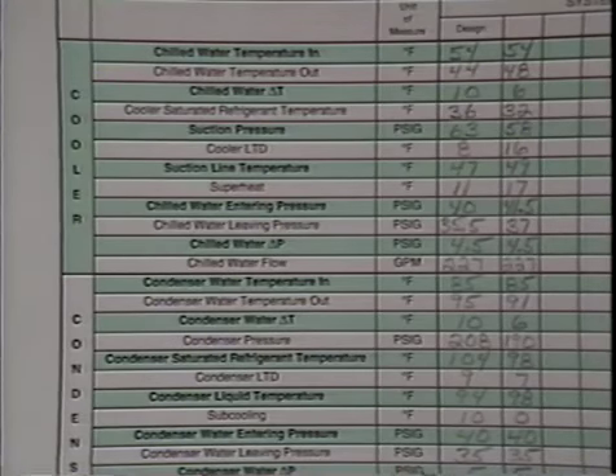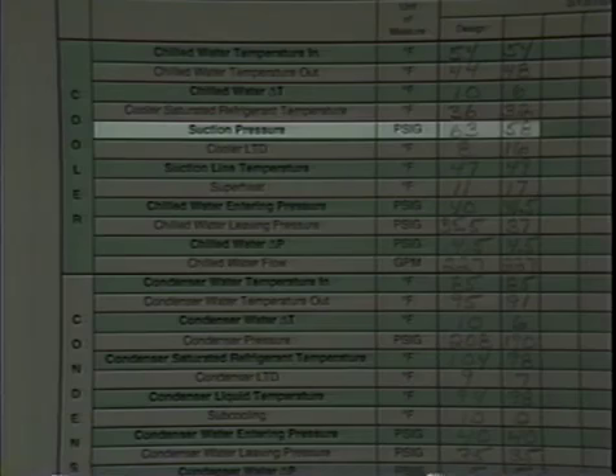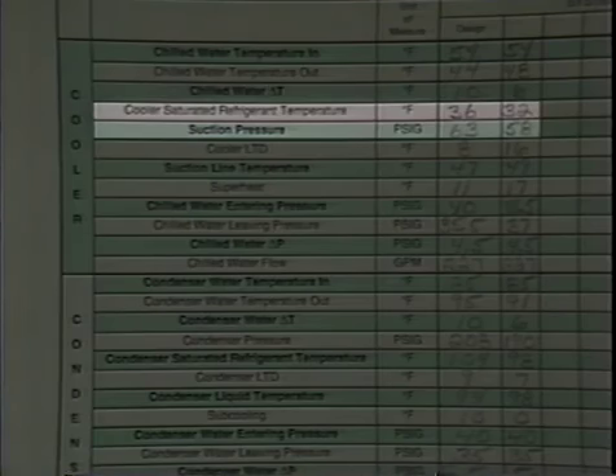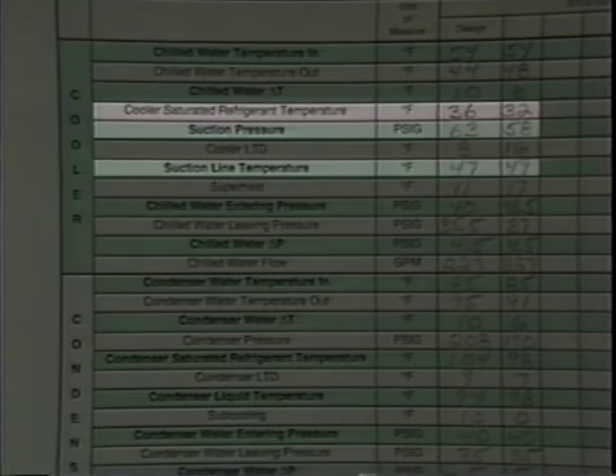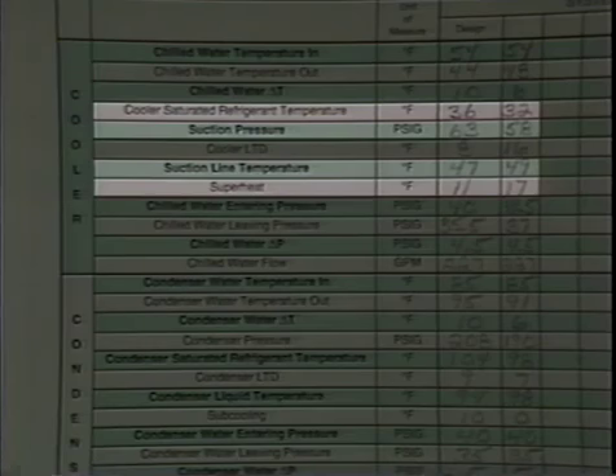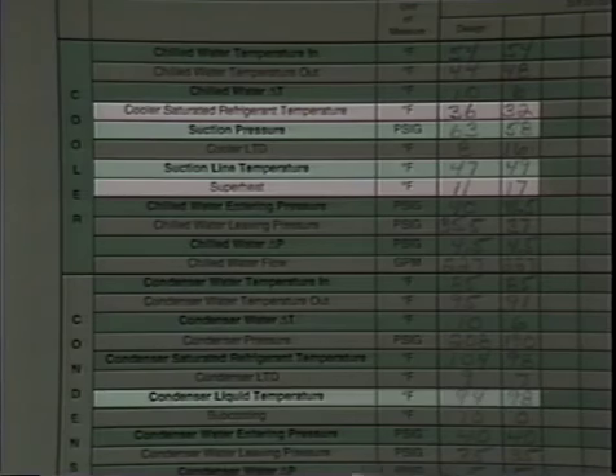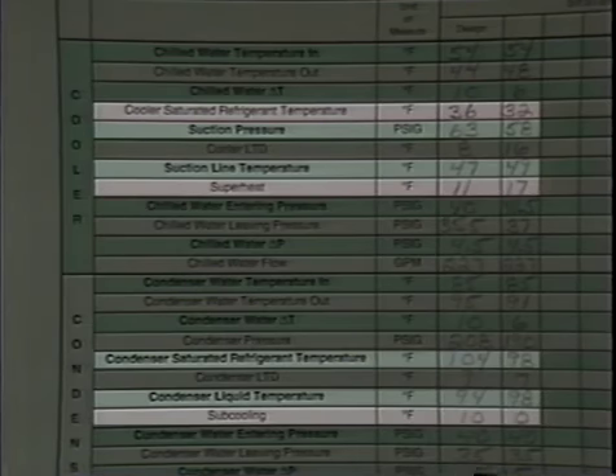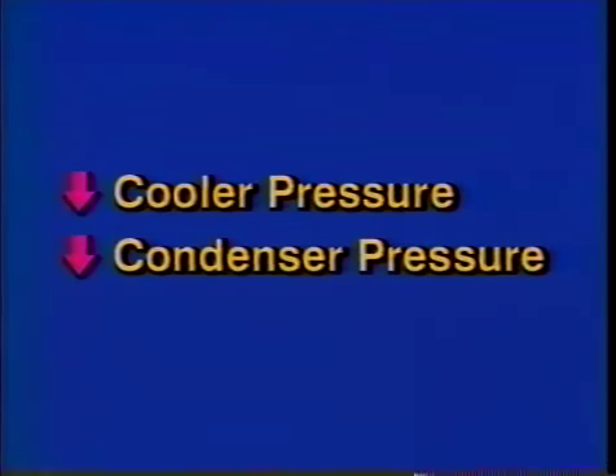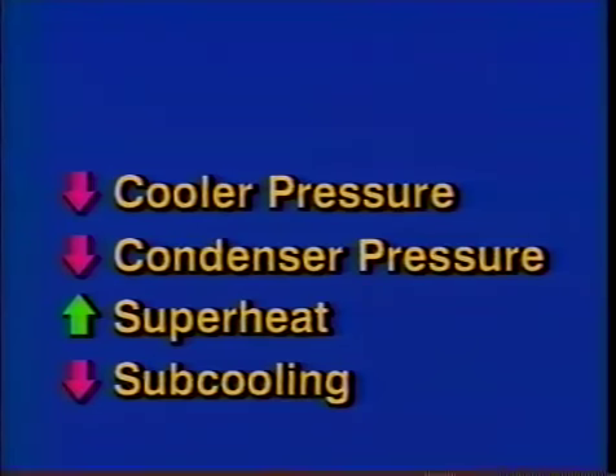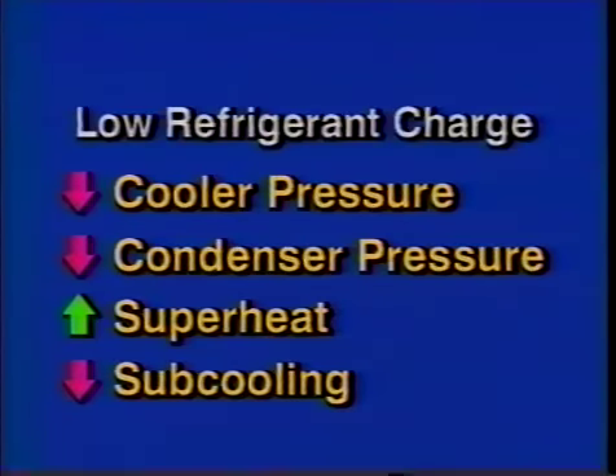There are a few more pieces of data that are pertinent. The saturated suction pressure is 58 psig, giving us a saturated cooler temperature of only 32 degrees Fahrenheit. That's 4 degrees low. And the actual suction gas temperature is 49 degrees, giving us a superheat of 17 degrees, 6 degrees higher than the normal 11 degrees. Looking at the condenser, we see the leaving liquid temperature is 98 degrees and the refrigerant is condensing at 98 degrees. So we have no subcooling at all. If we put all this together, cooler and condenser refrigerant pressures are low, superheat is high, and subcooling has been lost. We find we have the classic symptoms of low refrigerant charge.